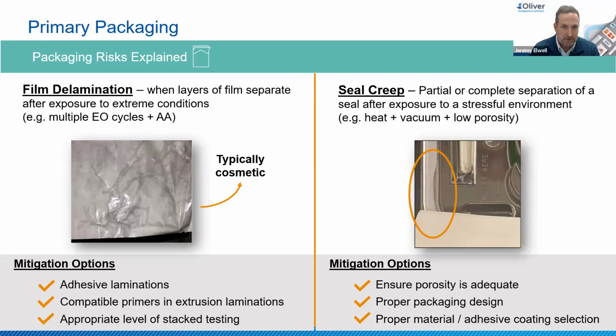And then another risk is seal creep. Seal creep can be defined as partial or complete separation of a seal after exposure to a stressful environment. Within sterilization, in many types of sterilization, you have a combination of sometimes heat and vacuum. When you combine that with low porosity or blocking porosity, you could have a difficult time getting the air in and out, and it could put stress on your seals. So some mitigation options are ensuring porosity is adequate, using Tyvek or even medical papers, and ensuring that is adequate in the design. But also the packaging system design and protective packaging, making sure you're not blocking that porosity, is essential as well. And proper material and adhesive coating selection comes into play. We'll talk a little more about that on the next slide.